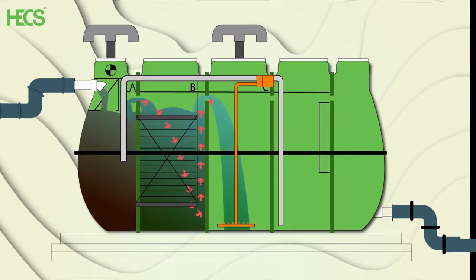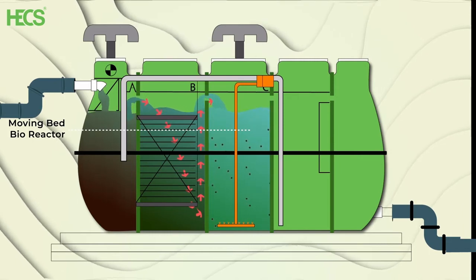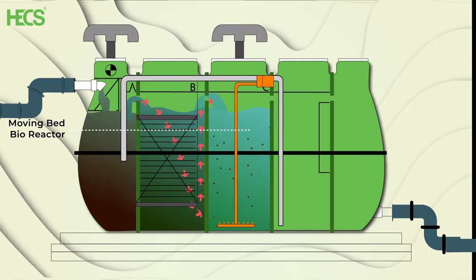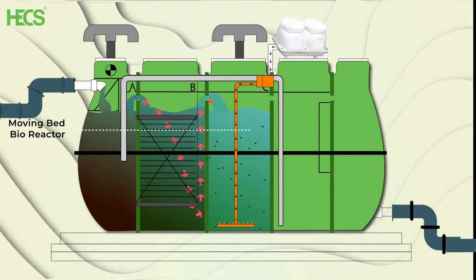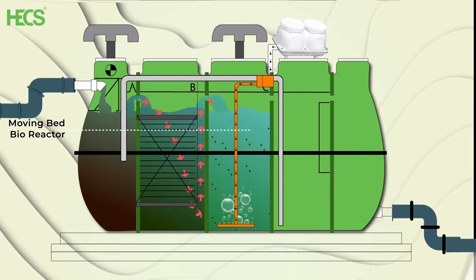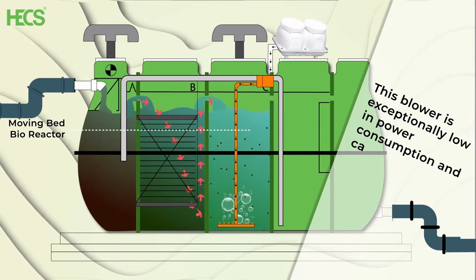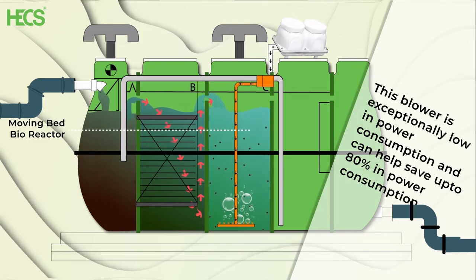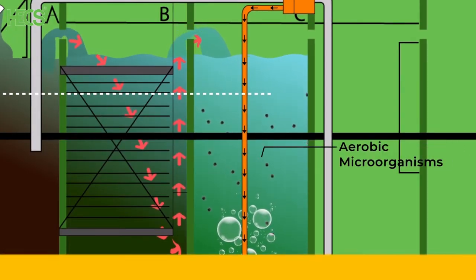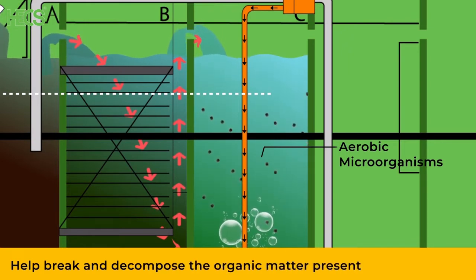The partly treated sewage then flows into the MBBR or moving bed bioreactor, which consists of MBBR media. Continuous aeration is provided to this chamber through a magnetic diaphragm blower. This blower is exceptionally low in power consumption and can help save up to 80% in power consumption. The aerobic microorganisms present help break and decompose the organic matter present in the sewage.